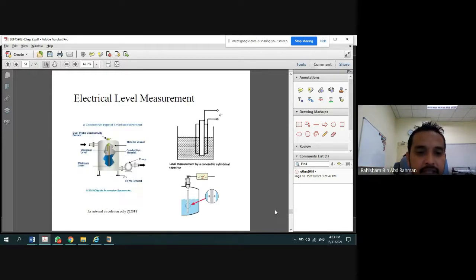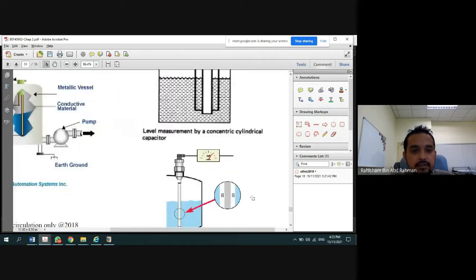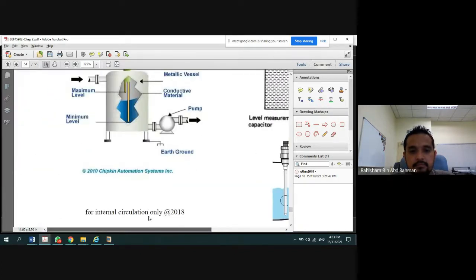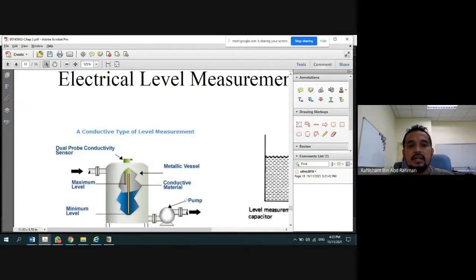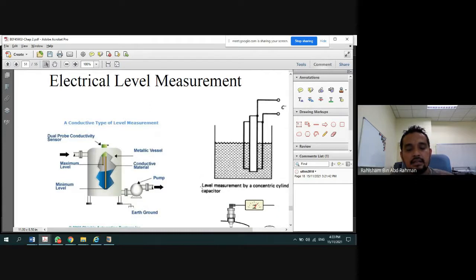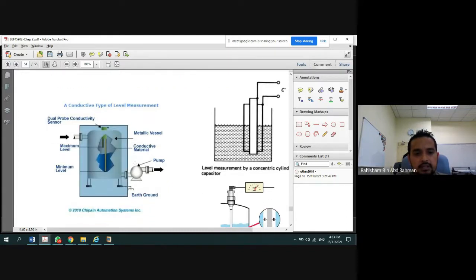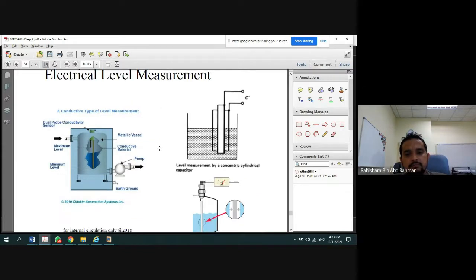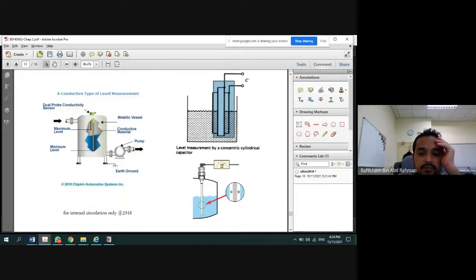Electrical level measurements. Looking here, a conductive electrical level measurement. Earlier there was one mechanical part, and now we go to electrical. We have a minimum level and a maximum level, and we have probes. We have a probe installed here, and a vessel, and this is earthed. Everything is connected to this, which is a capacitor, electrical level. We measure in terms of the electrical.